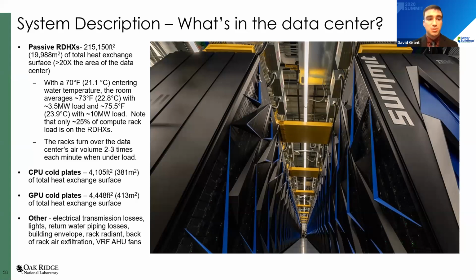And then we have the cold plates, CPU cold plates and GPU cold plates. And then the other losses that are inside the data center that the cooling system has to take care of are the electrical transmission losses, the lights, and the return water piping losses. Because our water temperatures were so warm, and close to the ambient temperature, we did not insulate that pipe. And then there is some rack bypass that occurs where hot air escapes without going through the rear door heat exchangers. And then we have a VRF system, which is purely there just for filtering the data center air and then trimming if we needed it. But the VRF system does not handle any of the sensible heat that's dumped to the data center from any of the IT equipment. Next slide, please.